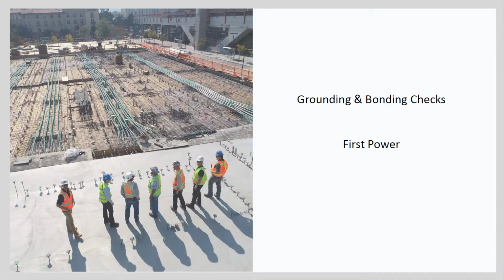So some other typical checks, some of the easier checks would be grounding and bonding checks before the power is applied. The integrity of the grounding system and bonding system needs to be verified. You want to check this before first power is applied because if there is any issues during energization, this is the system that will direct hazardous energy to ground and protect the equipment and protect any people that are working in the area. Grounding and bonding checks are typically confirmed visually or can be measured with a multimeter measuring the resistance of bonds to ensure low impedance bonding to all metallic surfaces in place.